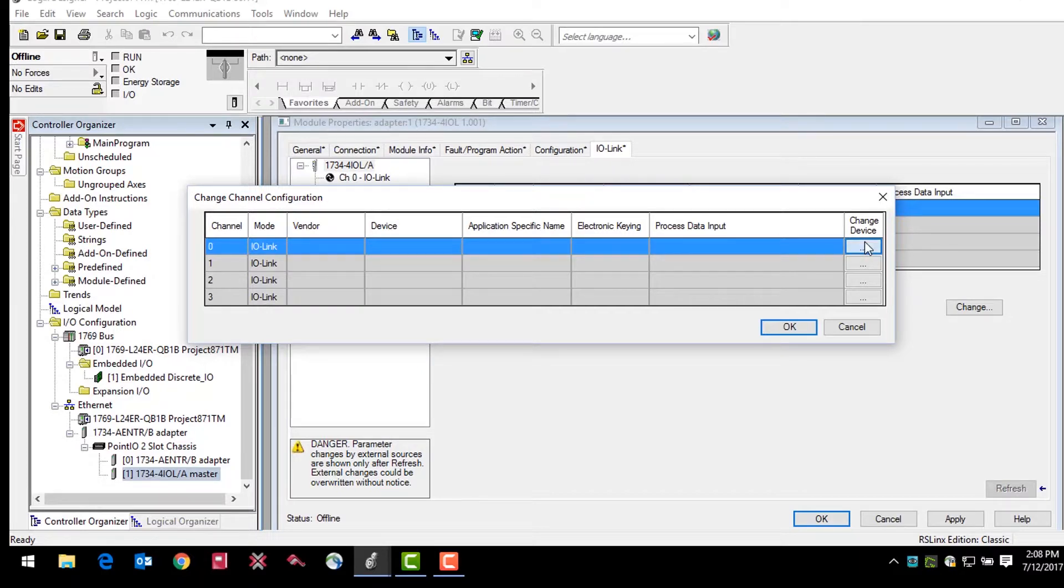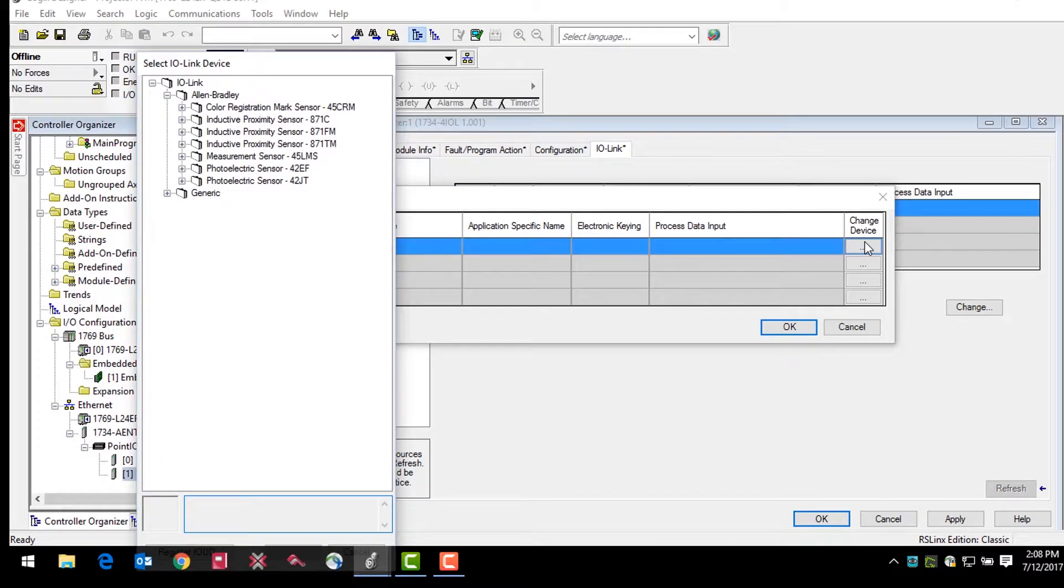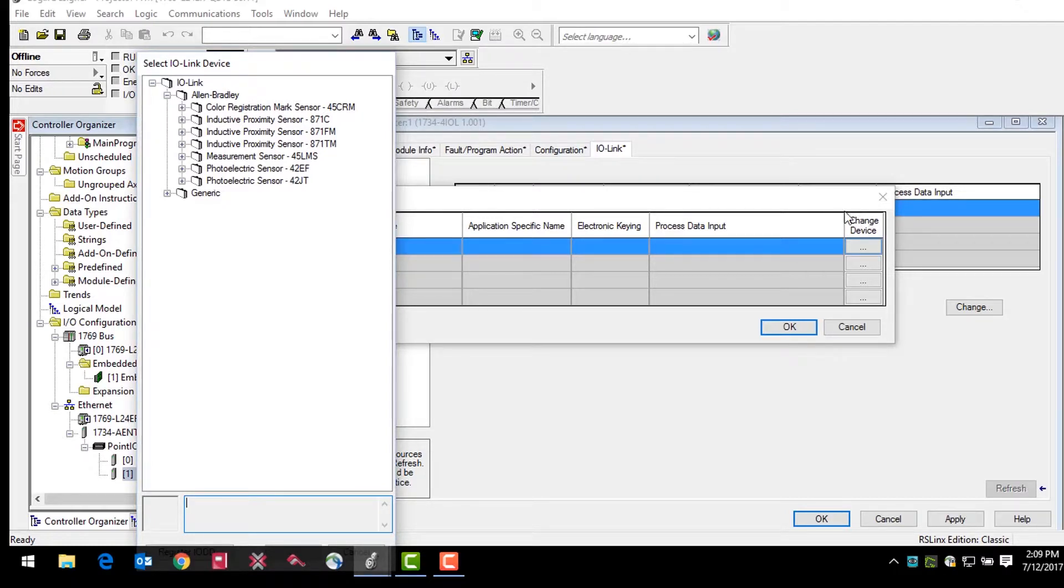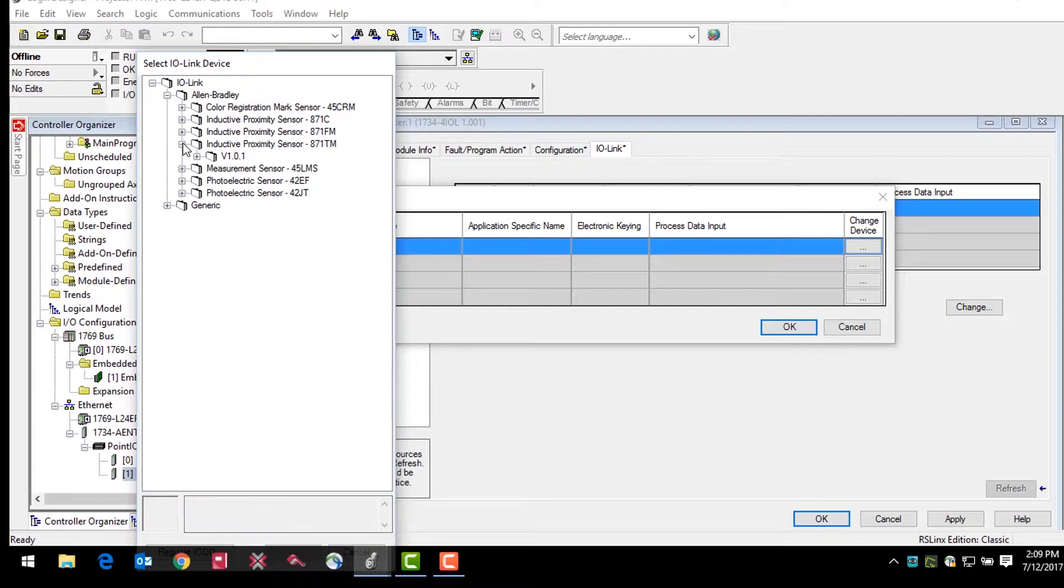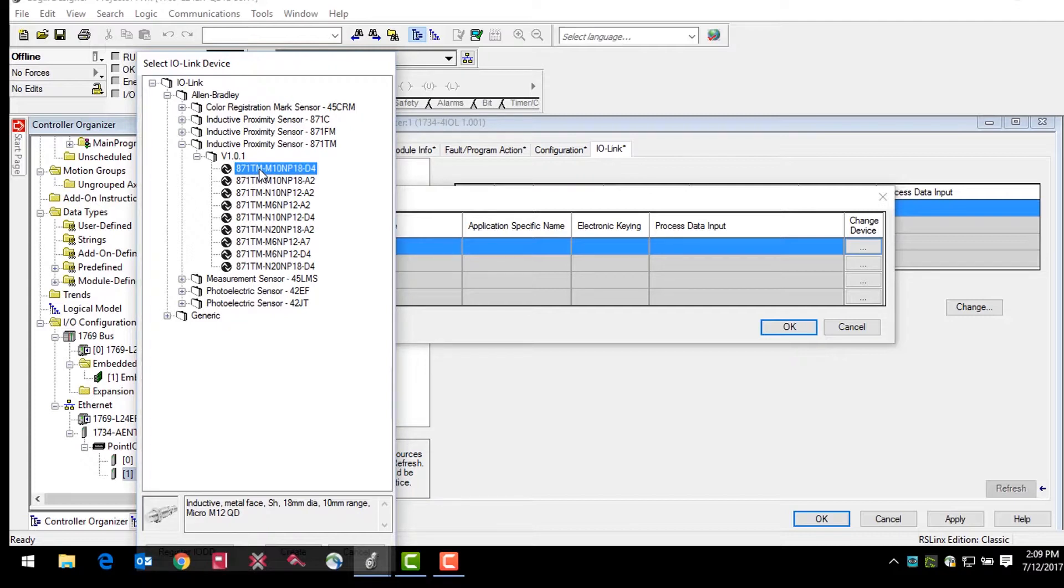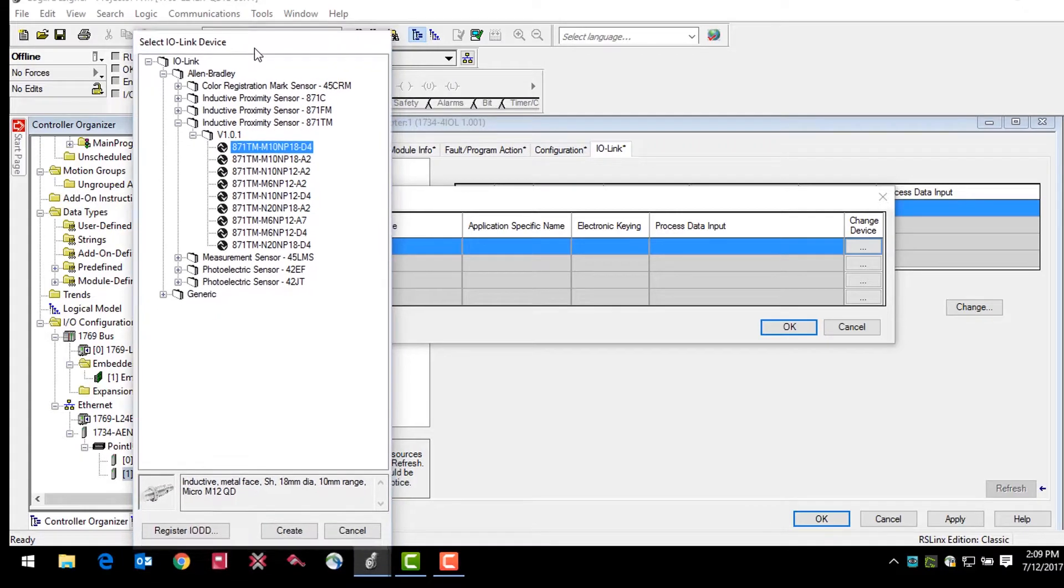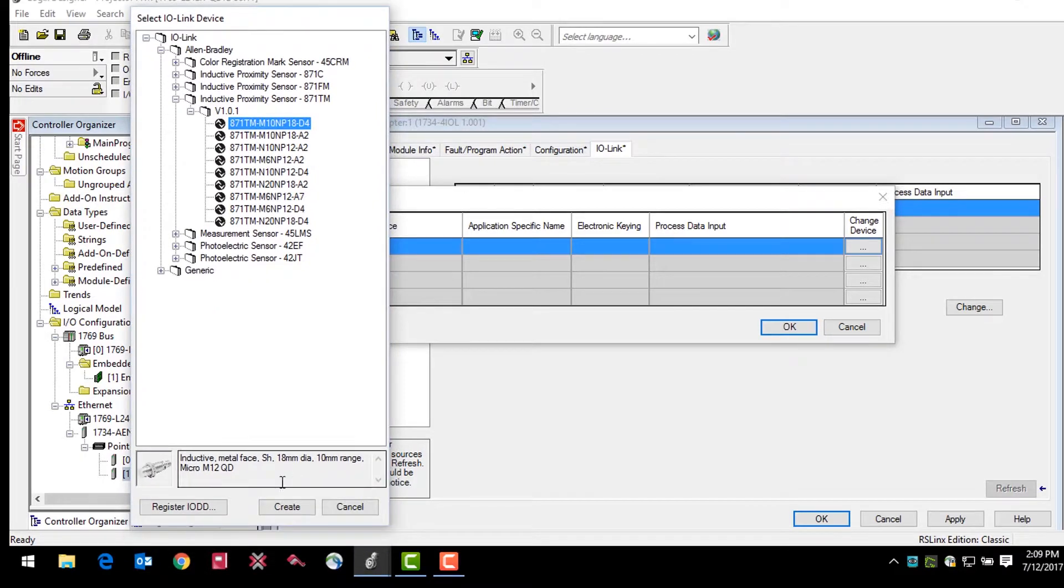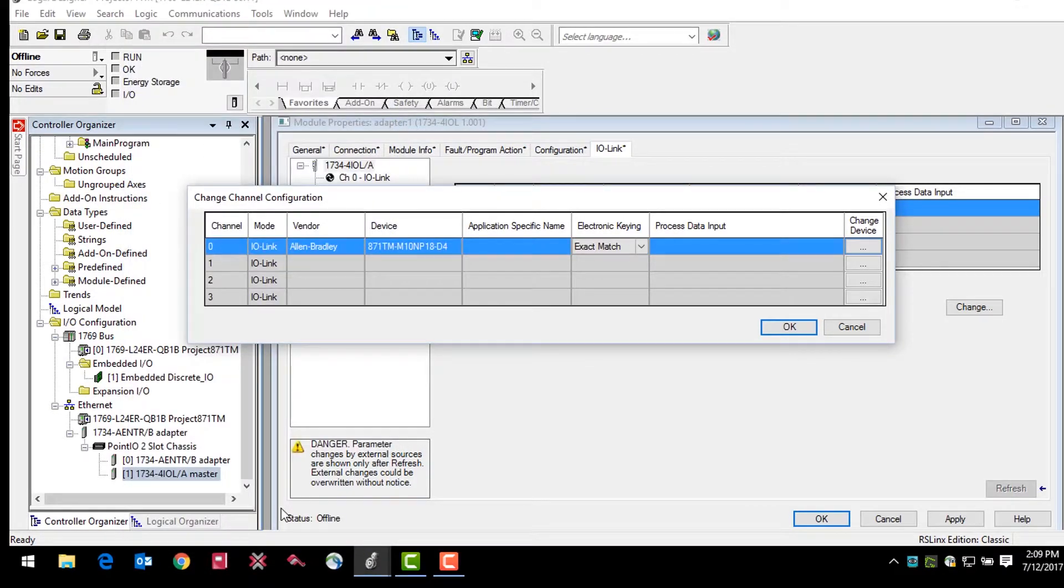This will bring up a device tree of possible sensors to connect the master module. In this example, we'll be adding a 871TM M10NP18D4 inductive proximity sensor. Select that sensor and then click create at the bottom of that window.